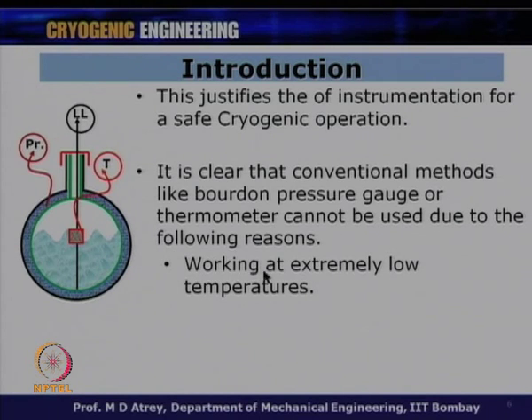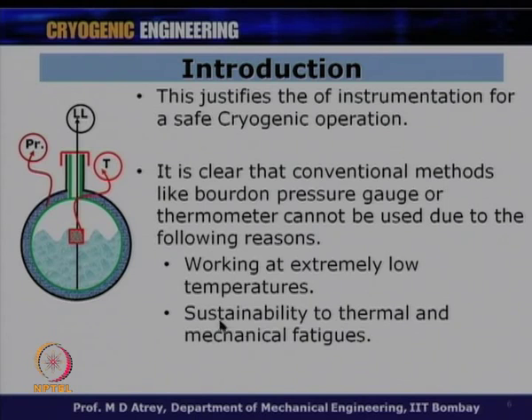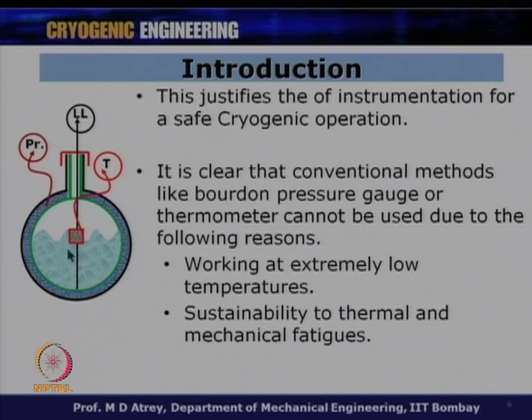Sensors must work at extremely low temperatures. For instance, a mass flow sensor measuring boil-off must withstand those low temperatures, and a liquid level sensor inside the liquid must also stand them. Materials undergo significant changes at low temperatures, so sensors must be correctly made. Additionally, sensors must sustain thermal and mechanical fatigue—the repeated cycling between room temperature and cryogenic temperature causes expansion and contraction, which the sensor must withstand.